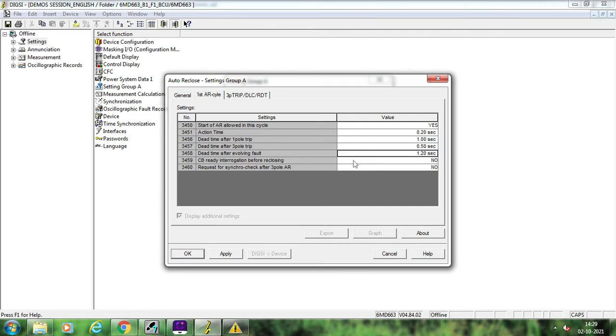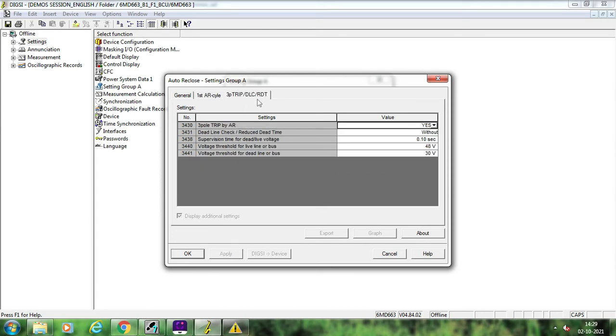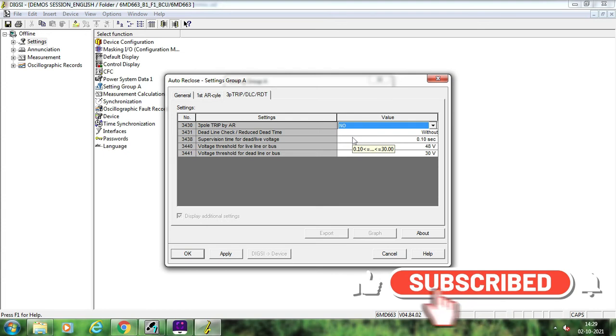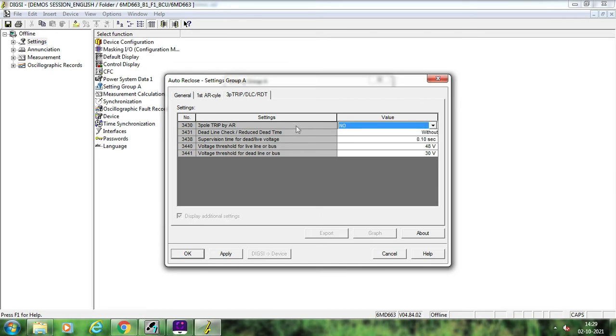The next thing is CB ready interrogation before reclosing — the BCU will check the CB ready signals through the masking IO and if the CB is ready before closing, only then will it issue a closing command; otherwise it will issue an auto-closure block or three-pole trip. Set it as yes or no depending on your requirement. Regarding three-pole trip by auto-reclosure: keep this as no if pole discrepancy relays are available in your substation. If pole discrepancy relay is not available, then you must select yes. Generally pole discrepancy relays are provided in all transmission substations, so you keep this as no. If you keep this as yes, during auto-reclosure time the BCU will issue a three-pole tripping command and the auto-reclosure cycle may not complete.